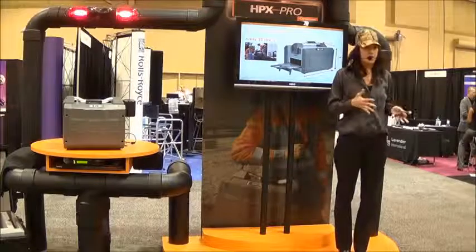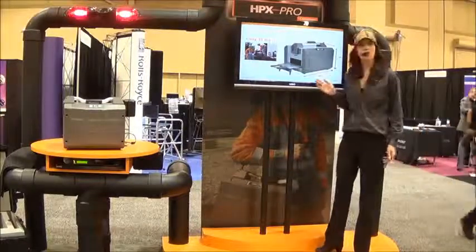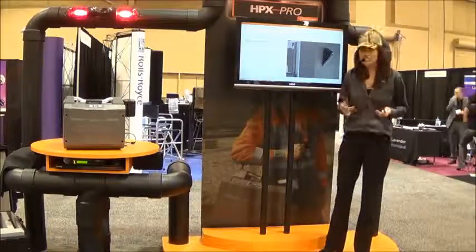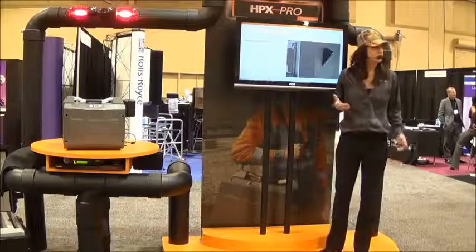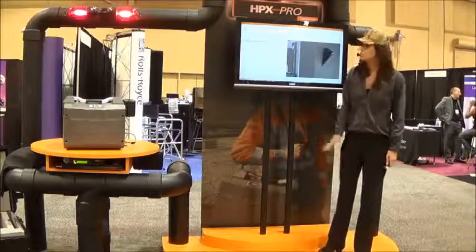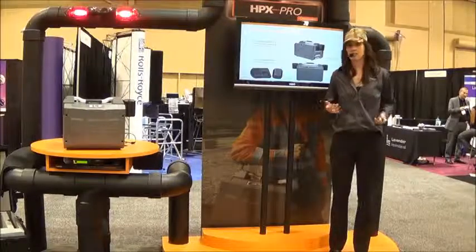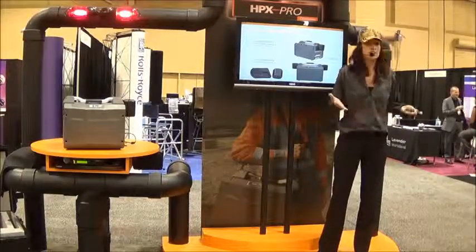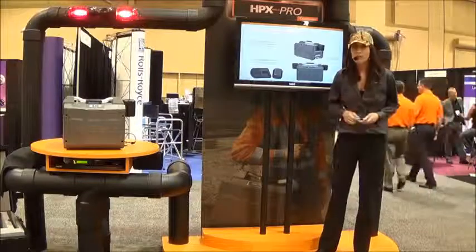Let's look at the basics. Being both compact and light, it's ideal for narrow-width imaging applications in non-destructive testing. The HPX Pro weighs in at only 35 pounds, and it's designed to handle the rugged environments NDT throws at it. All the optics are located above the scan area and sealed to prevent dirt intrusion. Both the entry and exit doors fold up to seal off dirt and dust during transport, and the replaceable air filter keeps ingested air clean. The unit has multiple power options — it can operate on main power or with a common 24-volt power tool battery, and delivers 45 minutes of runtime per charge.